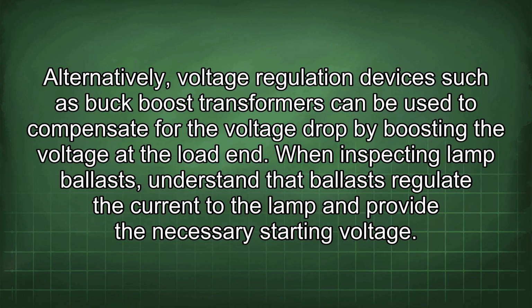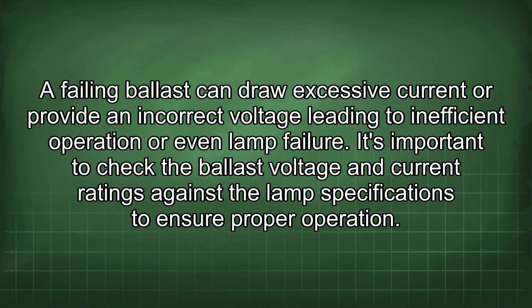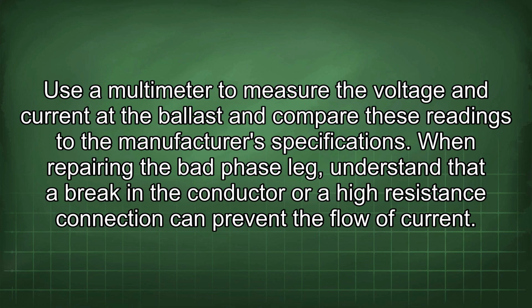When inspecting lamp ballasts, understand that ballasts regulate the current to the lamp and provide the necessary starting voltage. A failing ballast can draw excessive current or provide an incorrect voltage, leading to inefficient operation or even lamp failure. It's important to check the ballast voltage and current ratings against the lamp specifications to ensure proper operation. Use a multimeter to measure the voltage and current of the ballast and compare these readings to the manufacturer's specifications.